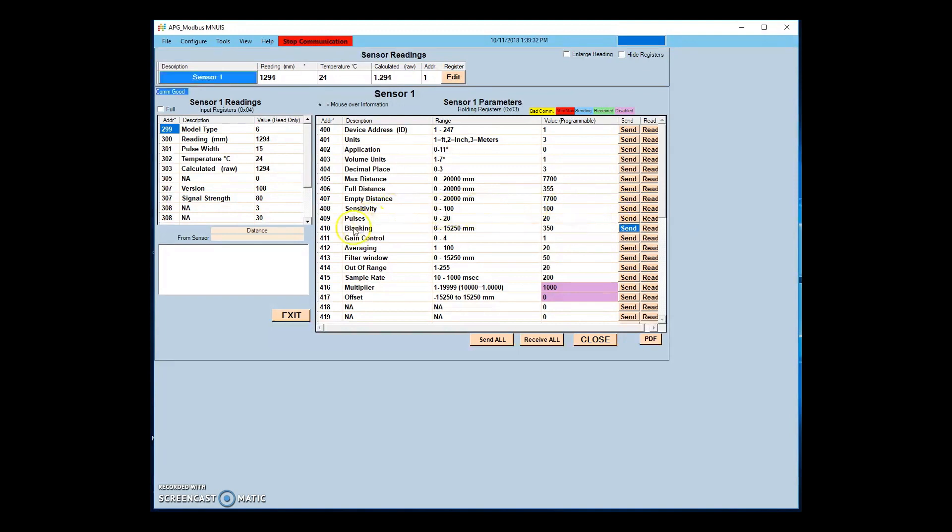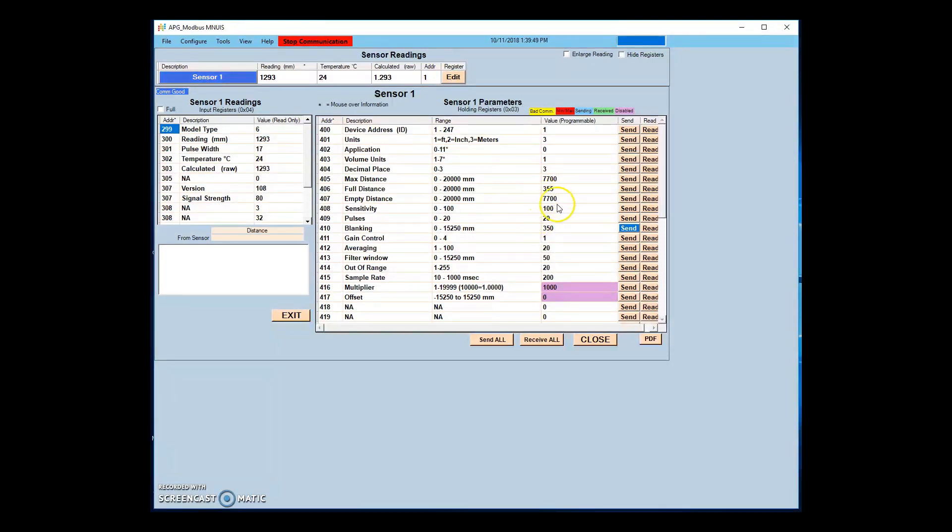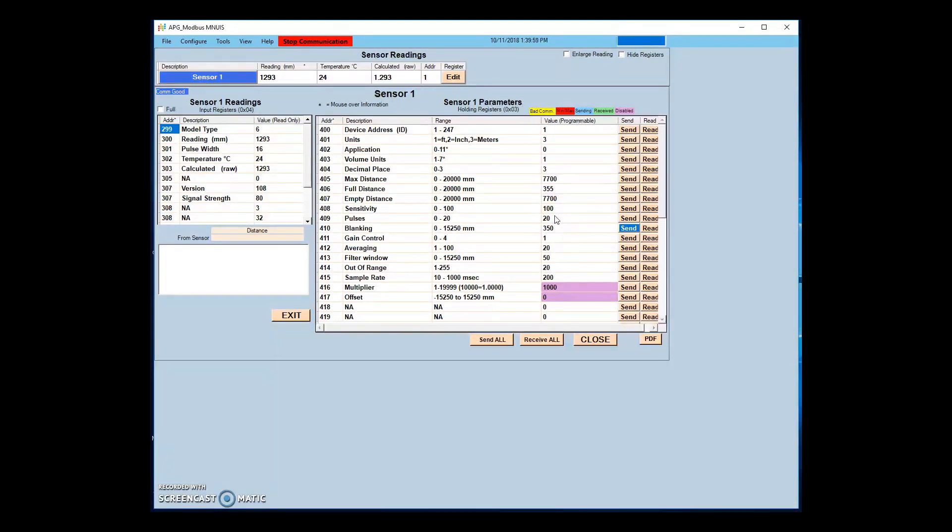Gain control allows you to choose between programming the sensor gain settings manually or allowing the sensor to automatically adjust to optimize its signal. If the sensor is in AutoSense, sensitivity and pulses will be determined and optimized by the sensor with no user input. In HardTarget or SoftTarget mode, the sensor will determine the best settings using the entered Sensitivity and Pulses parameters as limits. In Manual mode, all changes to parameters must be made by the user.